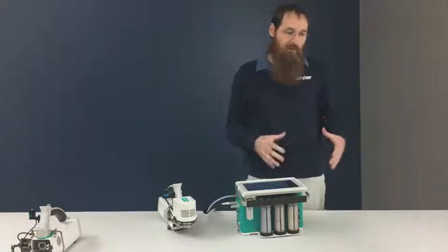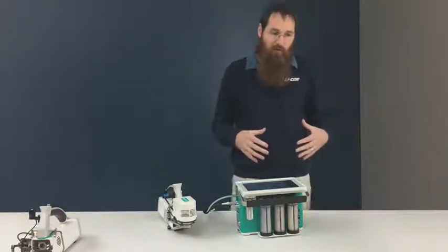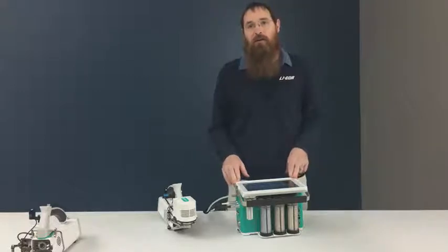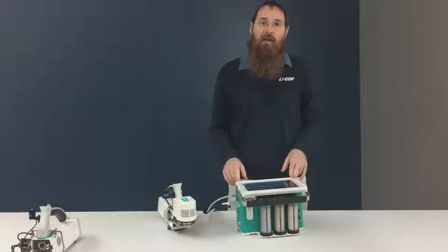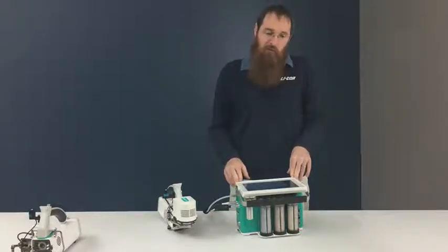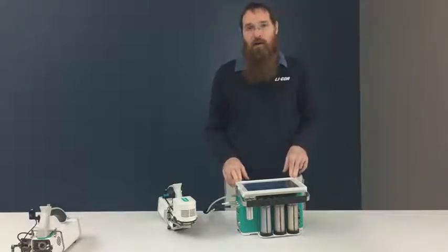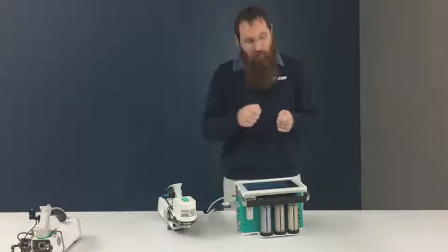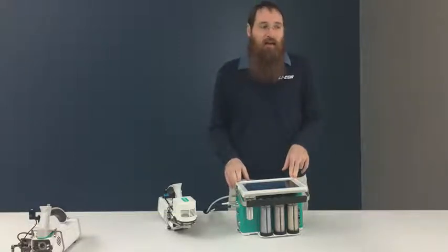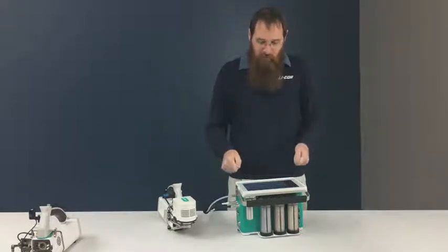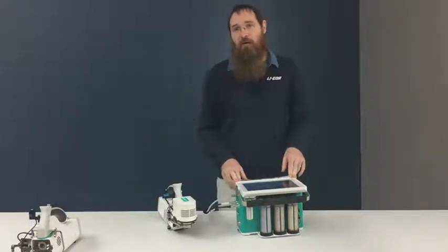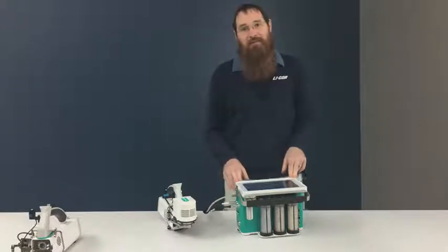So if you were a 6400 user and you were getting it ready to go into the field, you would open up book 1 of the user manual and go to page 1 of chapter 4, and there'd be this checklist of things that you would go through. That checklist would require you to push buttons and turn knobs and shake things and touch thermocouples and get screwdrivers out and turn things. And after 20 or 30 minutes of your time working with the instrument, you would know that the instrument's working well and you can take it out and go make measurements with it.